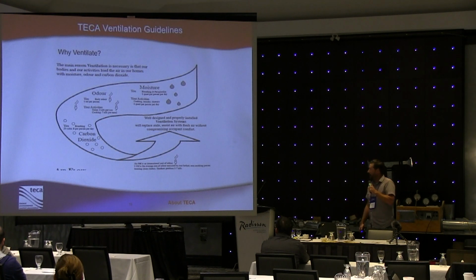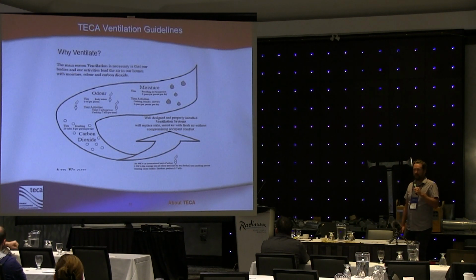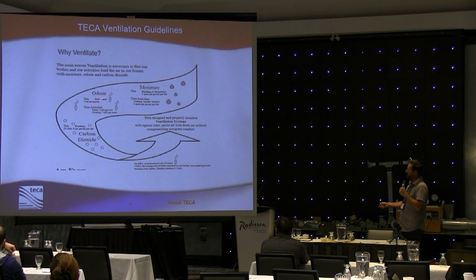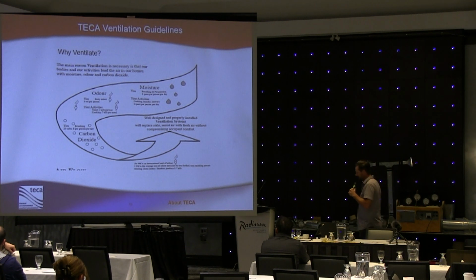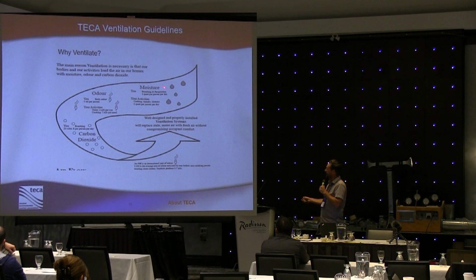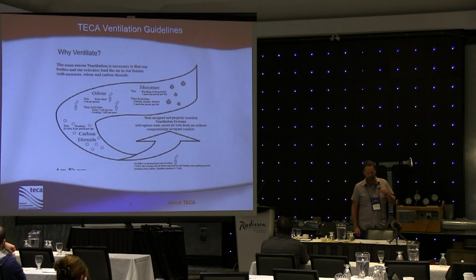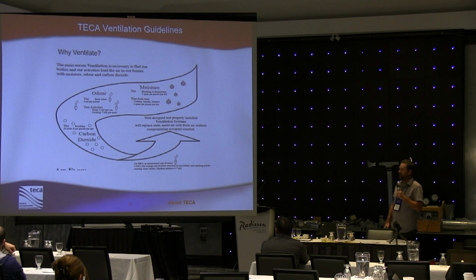So when we talk about why we ventilate, the primary reasons that we ventilate these residentially occupied buildings is that we want to get rid of these primary contaminants. Moisture being a big one. We want to get rid of moisture out of our indoor air. Very, very important that we take moisture away. We know the results of long-term moisture, high indoor humidity. We've got some problems with that.